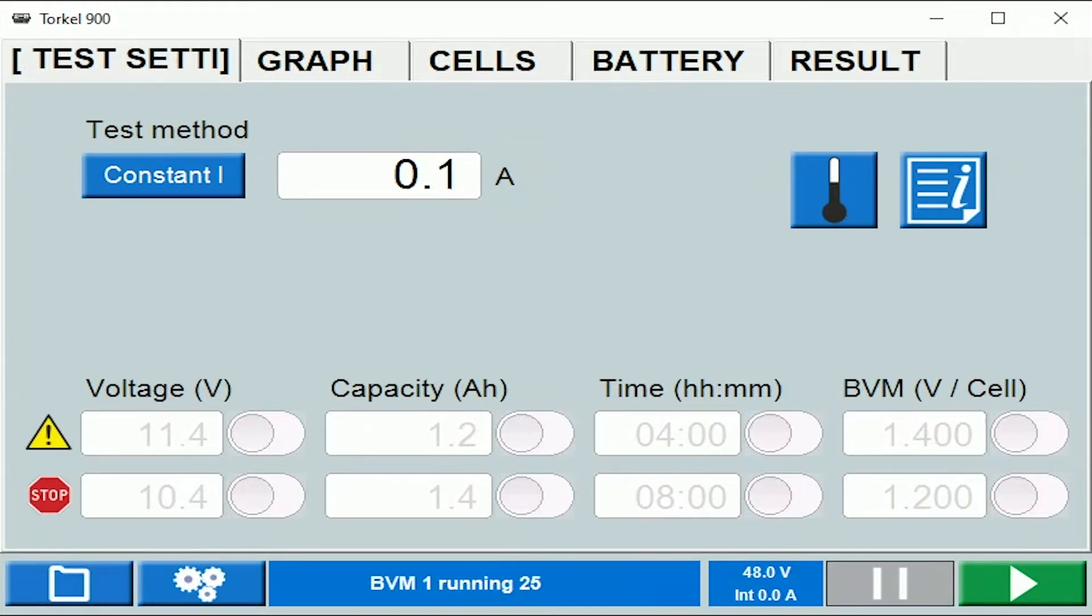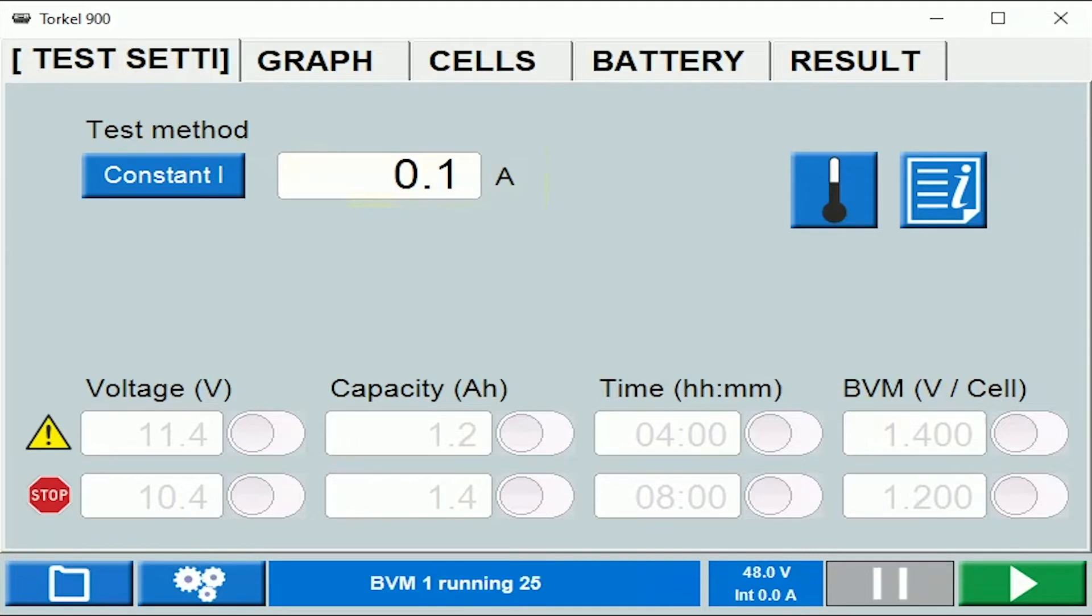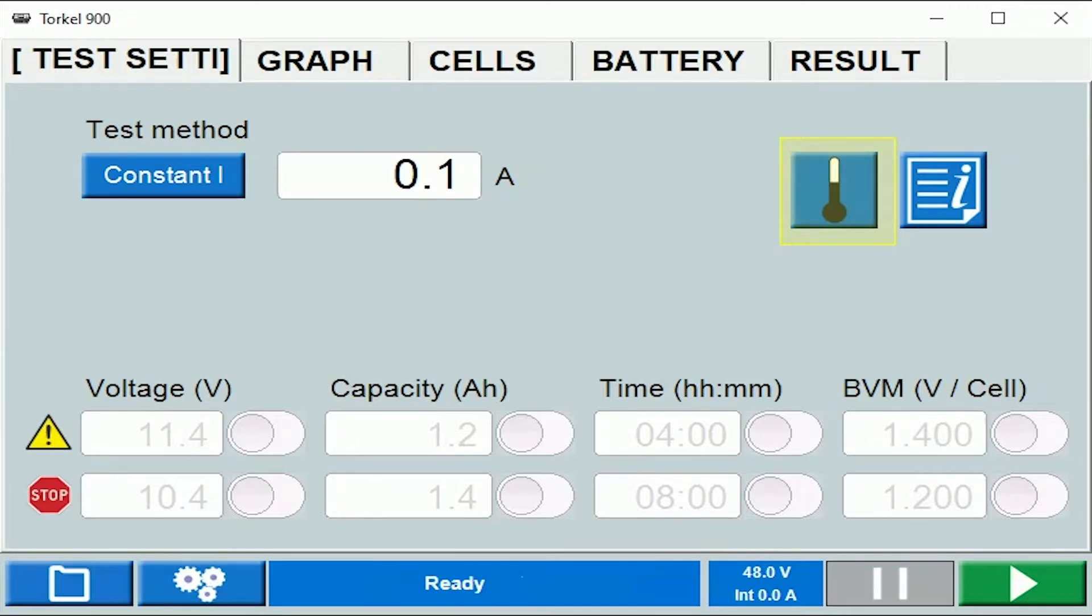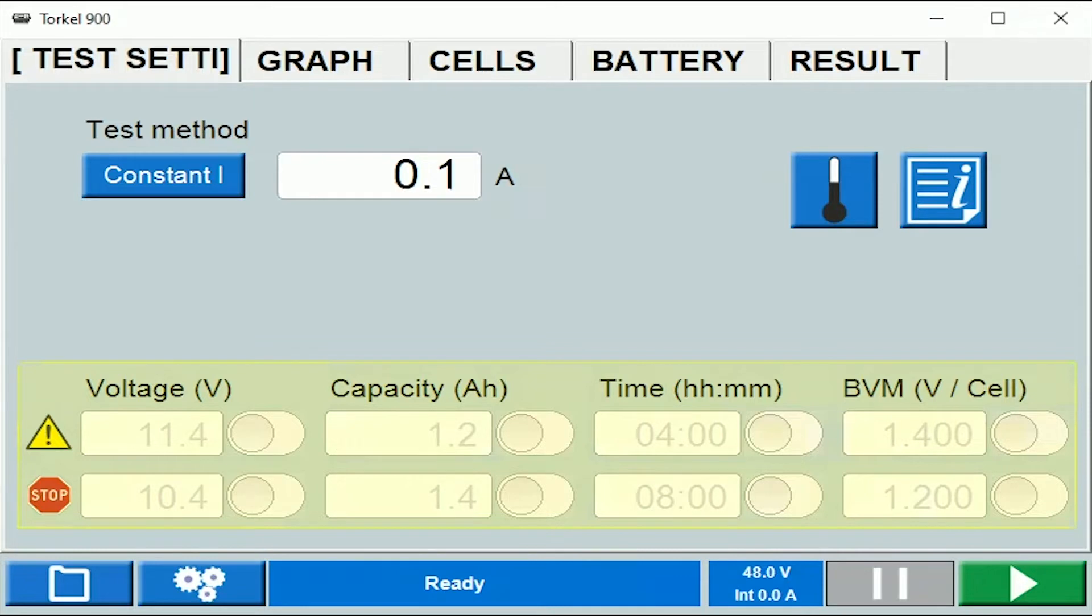You can type in the test current here, the current that you want to draw from the battery bank during the test. You can select the temperature correction factor over here. You can set warning and stop limits on the basis of various parameters over here.